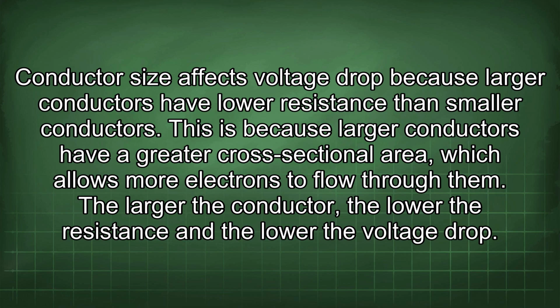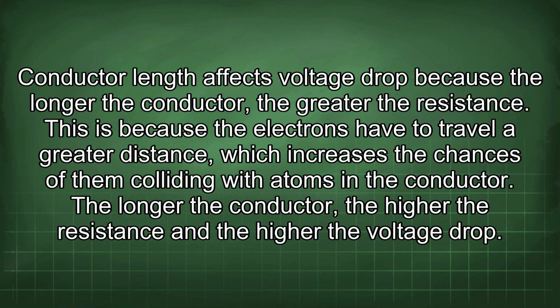This is because larger conductors have a greater cross-sectional area, which allows more electrons to flow through them. The larger the conductor, the lower the resistance and the lower the voltage drop. Conductor length affects voltage drop because the longer the conductor, the greater the resistance. This is because the electrons have to travel a greater distance, which increases the chances of them colliding with atoms in the conductor. The longer the conductor, the higher the resistance and the higher the voltage drop.